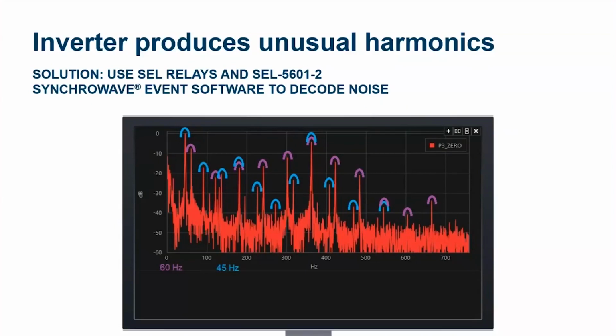And in this case, it turned out not to be an inverter. It turned out instead to be the engine and the generator. This was a 30 kilowatt generator and engine package. What we've now decoded from this harmonic analysis is that the blue hats were multiples of a 15 hertz harmonic introduced by the reciprocating, the bang of the piston, quite literally. In this case, these harmonics came from, in this engine, a sticky diesel fuel valve. It was a mechanically fuel-injected engine, and as such, we were able to actually decode which piston was having the problem from the 700 series relay.